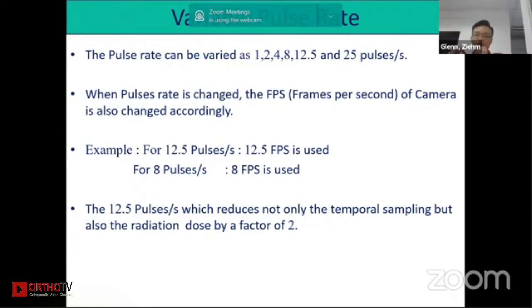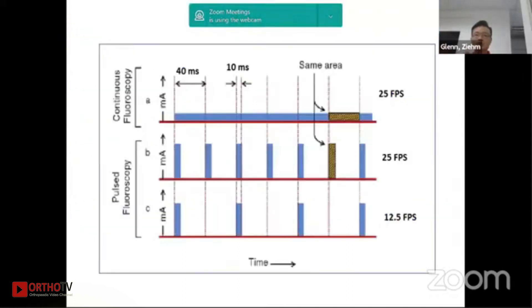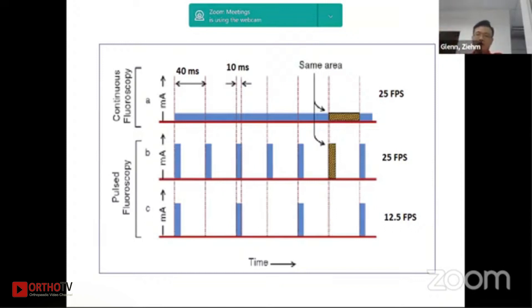12.5 pulses per second reduces not only the temporal sampling but also the radiation dose by a factor of two — so it's halved. As you can see, pulse fluoroscopy can still achieve the best image quality but at the lowest dose, so there is significant dose saving.